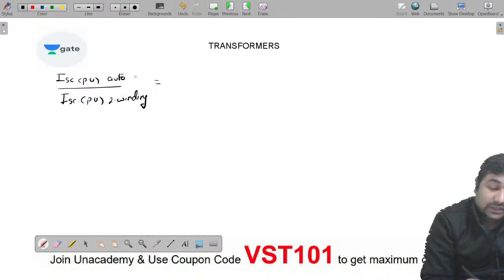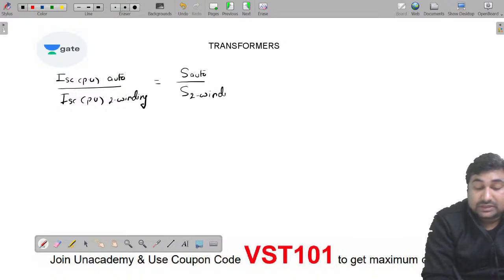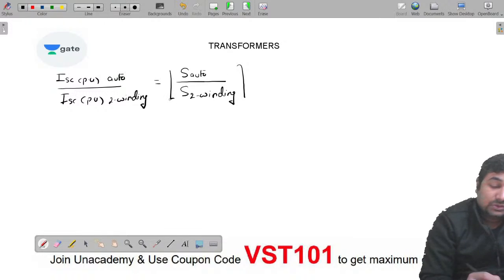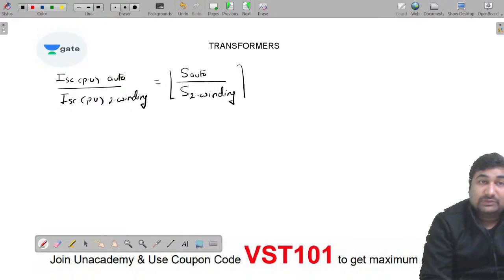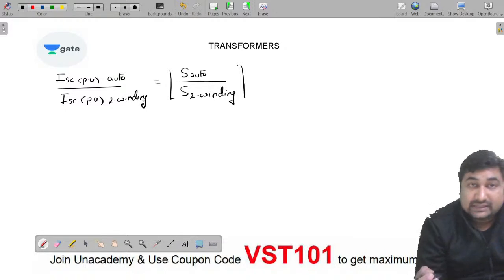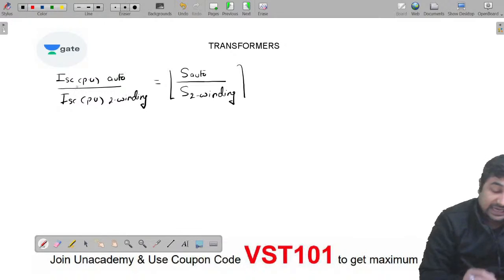Now please see, short circuit current can be represented as kVA of auto transformer to kVA of two winding transformer. Is it okay? Yes, sir. So the times by which the kVA capacity increases, by the same times the short circuit current is also increasing. It means the fault level is very high.